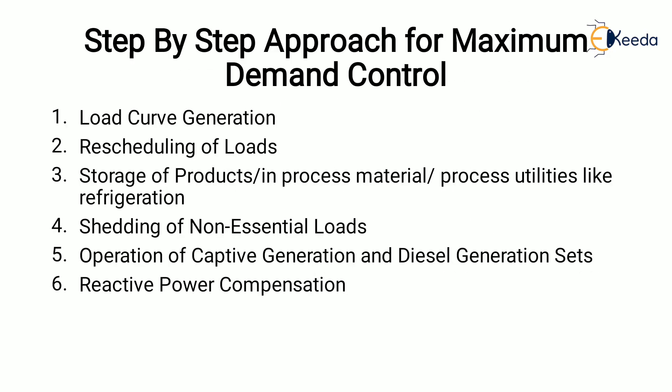Now let us see how maximum demand can be controlled. These are the step-by-step approaches for maximum demand control: first, load curve generation; second, rescheduling of loads; third, storage of products or process material and process utilities like refrigeration; fourth, shedding of non-essential loads; fifth, operation of captive generation and diesel generation sets; and sixth, reactive power compensation.